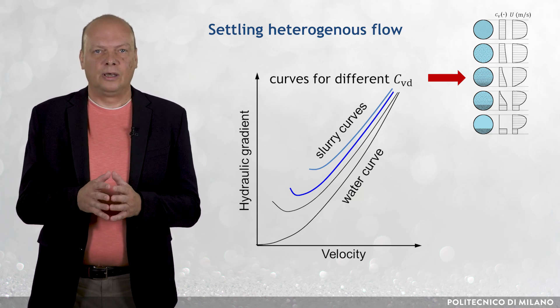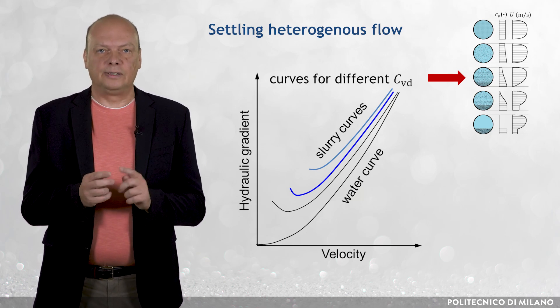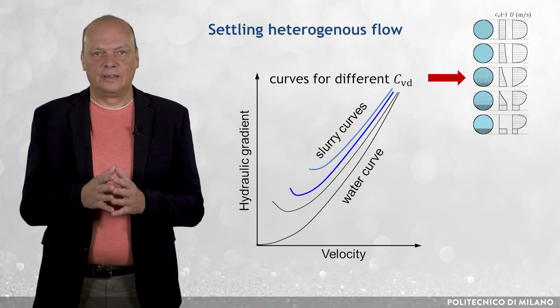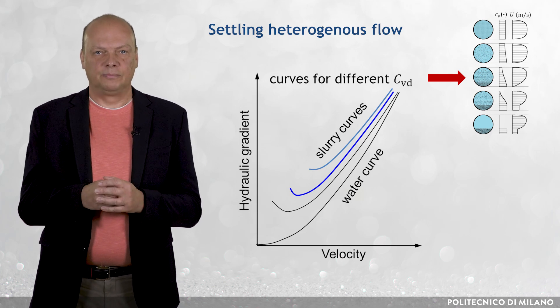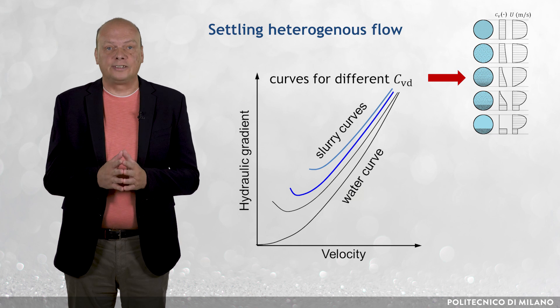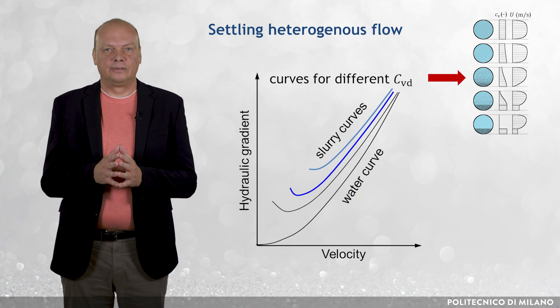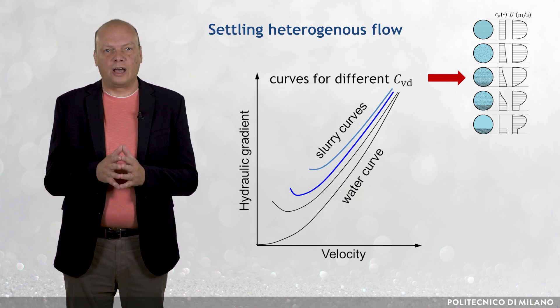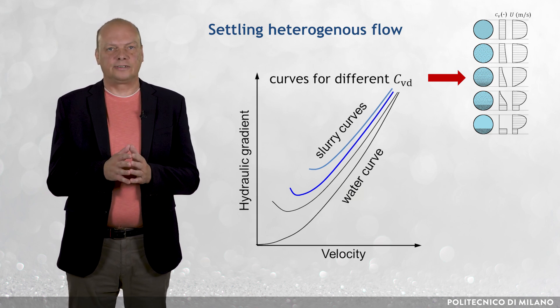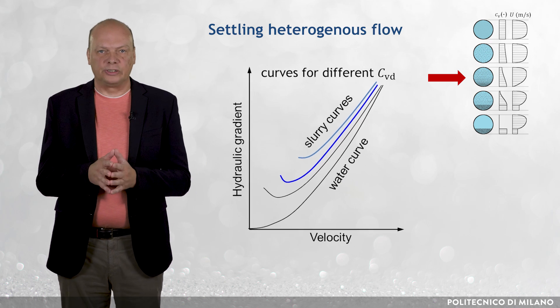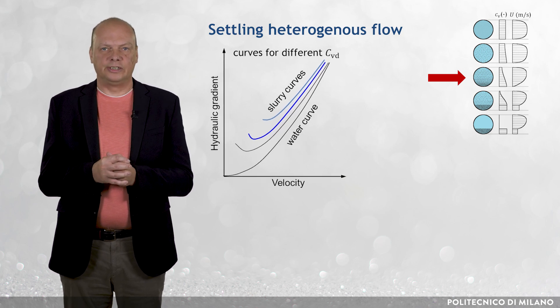The presence of the minimum on a pipe curve has consequences for the interaction with the pump characteristic curve, and hence for stability of operation of the pump-pipeline system. Note that if the flow velocity increases, the pipe curve tends to the curve of the carrying liquid, indicating that the contribution of solids to the total pressure gradient decreases with increasing velocity. This is due to the decreasing proportion of contact load particles with the increase of velocity in heterogeneous flow.